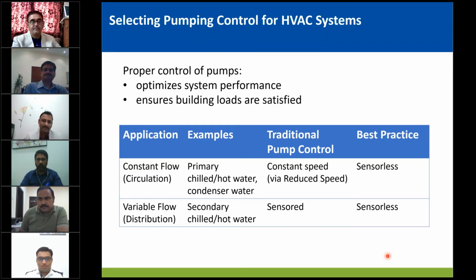So if we talk about a constant primary system, chilled water or hot water, we can also talk about condenser water. It's also constant volume most of the time. Now when it comes to constant speed or constant flow, traditionally we used to trim impellers to suit the actual operating point on site. And then when the variable speed controls came, we started reducing the speed and measuring the flow at the time of commissioning, which needs a flow meter. And we started achieving the flow at reduced speed.